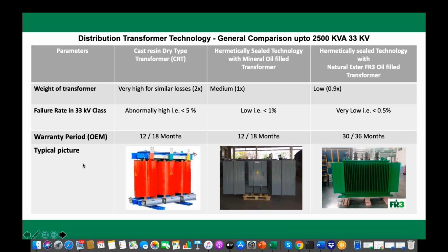A typical data, I don't want to name anybody, but what I have seen is as high as 5% to 6% failure rates in dry type transformers. Especially again, some of the data from Mumbai, when flooding took place, all the dry type transformers were submerged underwater and they could not recharge them. Few of them they could wash and recharge, but there was a significant failure there. Whereas most of the liquid filled transformers, almost 95%, they could recharge after the flood was over, and they just cleaned and started the transformer.